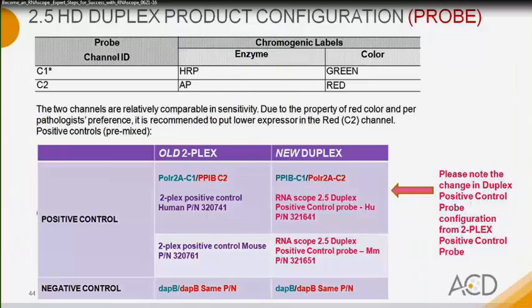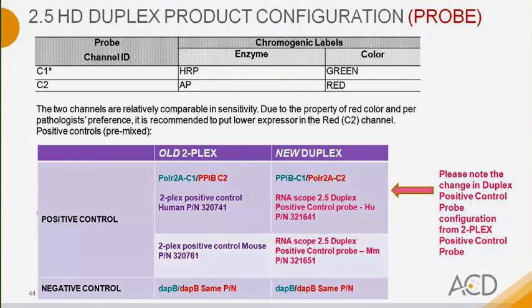For the probes, the compatible channels with the duplex reagent kit are channel 1 and channel 2, with channel 1 being HRP based and can be visualized in the green channel, and channel 2 being AP based can be visualized in the red. The two channels are relatively comparable in sensitivity, but due to the property of the red color, we recommend to put the lower expressor in the red channel as it appears to be brighter.